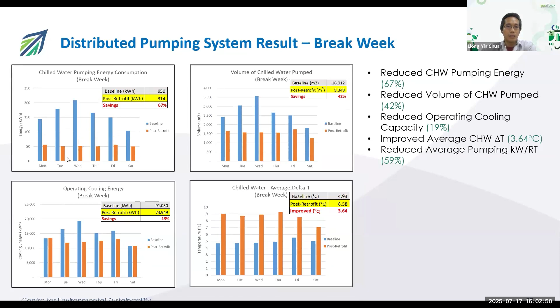If I remember correctly, the Shopee data center in Thailand is actually using the distributed pumping system right now, and there's a reduction of commissioning time of up to 80%. We've seen that the traditional system requires manual balancing, but for this system, because it's an individual control loop that won't affect other branches, the pump will just modulate itself to deliver the exact amount of water to the AHU, which is why there's such a huge reduction in commissioning time.